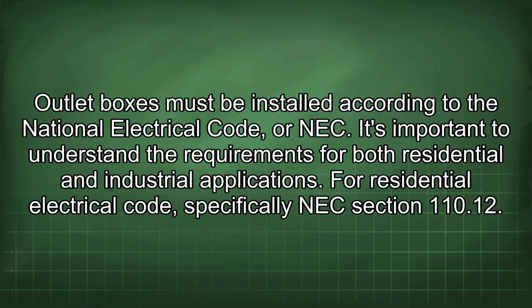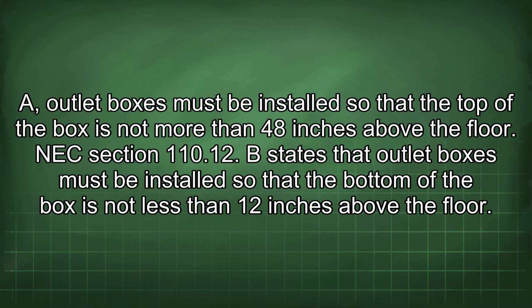For residential electrical code, specifically NEC section 110.12, outlet boxes must be installed so that the top of the box is not more than 48 inches above the floor. Section 110.12(B) states that the bottom of the box must not be less than 12 inches above the floor.